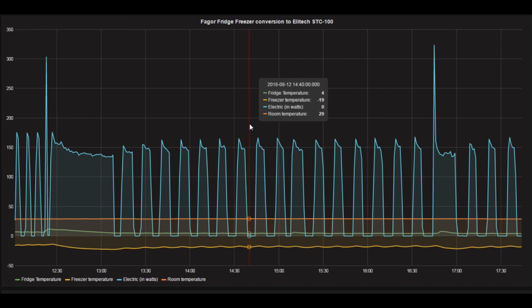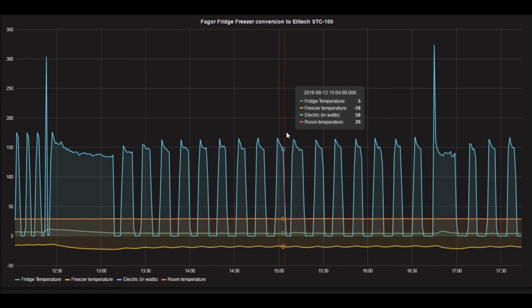So all I had to do then was go into F4 and add 4.5, because 4.5 is the difference between what the actual sensor is reading and what the air temperature is. So 4.5 plus the 0.5 which was set up on the thermostat gives us the 5 degrees, which is the air temperature, and that allows the controller to look correct on the dial - the air temperature from now on is what is shown on the dial.